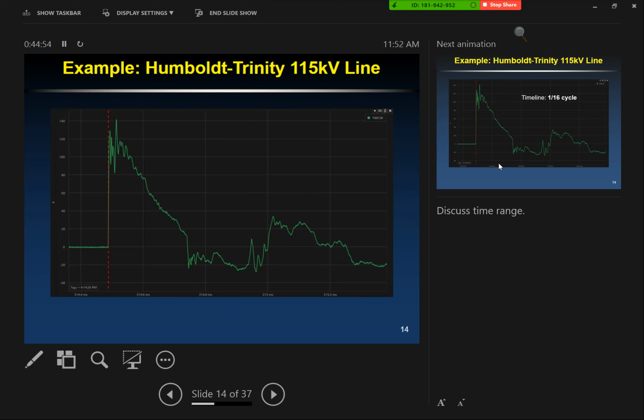But going through this example, let me point out here—this whole timeline we're looking at is 1/16 of a cycle, and the relay has filtered out all the 60 hertz anyway. You would see a little bit of a rise in this if they hadn't filtered out the 60 hertz. So all the action in a traveling wave event is not happening on a power system cycle like we're used to looking at. This is happening in 1/16 of a cycle for this 70-mile long line. For a shorter line, all the action is going to happen in maybe a 32nd of a cycle or 64th.